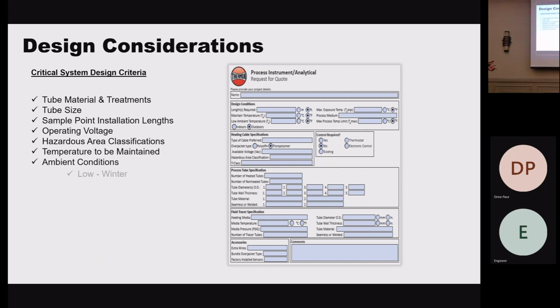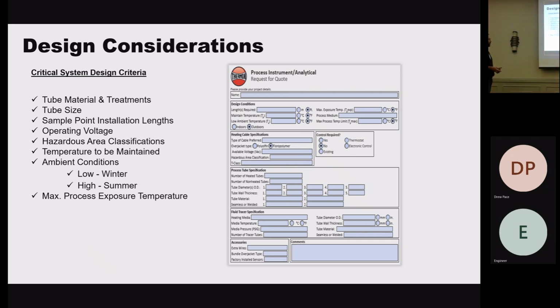Maintain temperature, ambient conditions, obviously. The max process exposure temperature is a big one. You don't really see it in CEMS because the gas loses temperature really quickly, but in power plants, the steam sample lines for sure. The picture we showed earlier was actually a buffer design. We have to move the heater cable away from the tubing to make sure it doesn't melt that PFA.